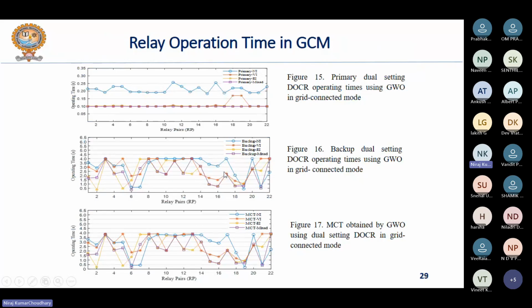Then this is for the backup dual setting relay time of operation. Here in the first one, you have seen that in seconds, when NI characteristics was used, the time of operation was somewhere between 0.2 second and 0.25 second. Now, for the same fault location and the relay pair, the backup relay time of operation you can see is around 3.5 seconds. So now you can calculate, depending upon the time difference between the operation of the backup relay and the associated primary relay, the CCT or MCT, measured coordination time, the actual measured coordination time interval, by subtracting the primary time of operation from the backup time of operation of the relay, and the MCT values are calculated for different types of relay settings.